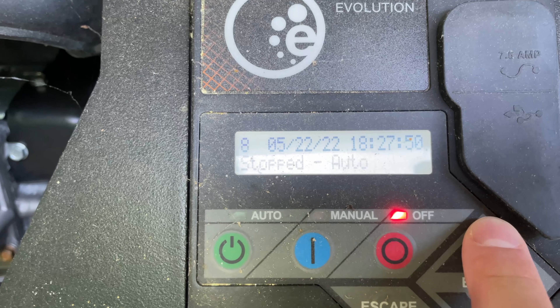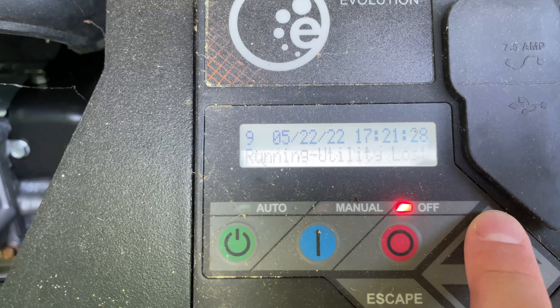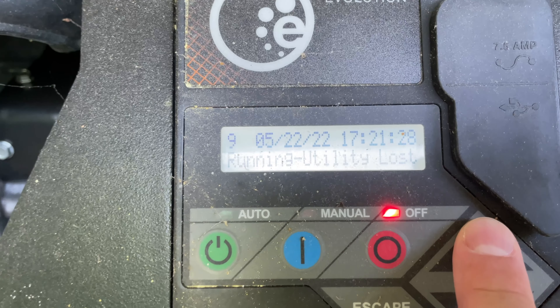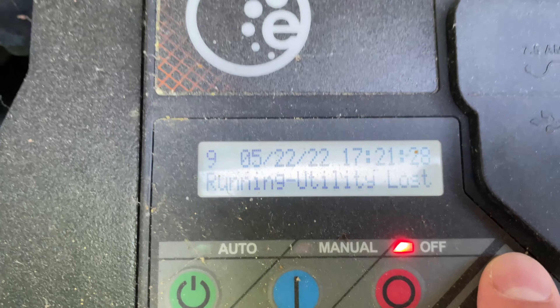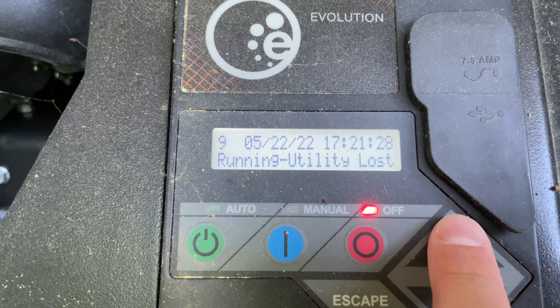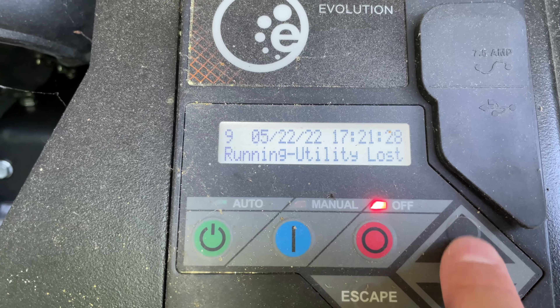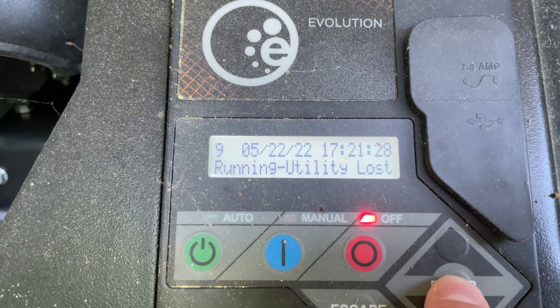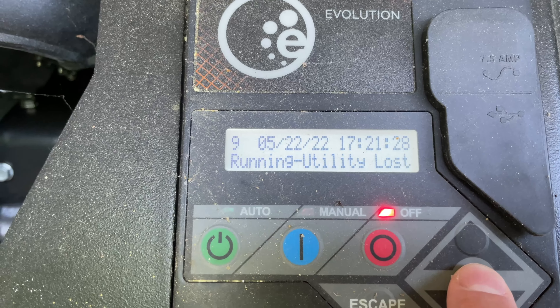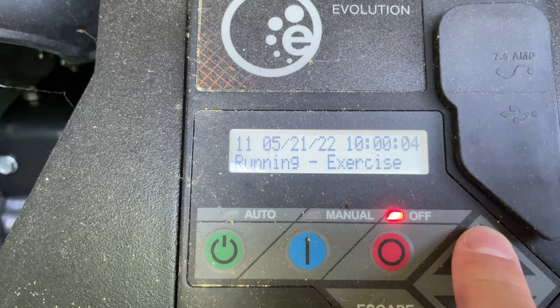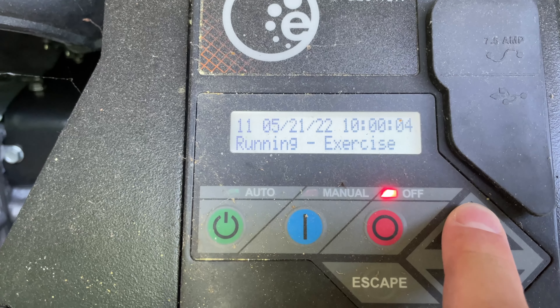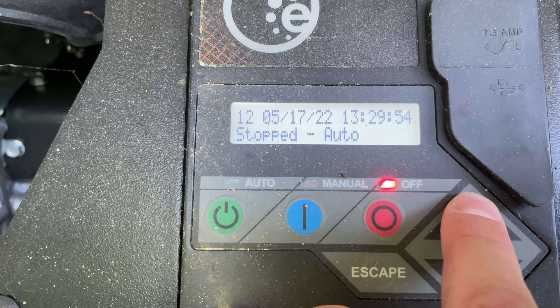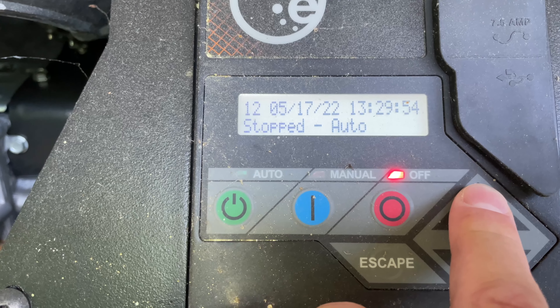You can scroll through the various days. Here's an entry at 18:27 — this right here was a loss of utility power, so it lost power from the grid. You can see that event ran for a while. You can scroll through and see the start times.